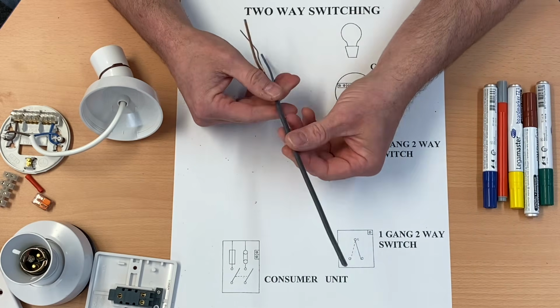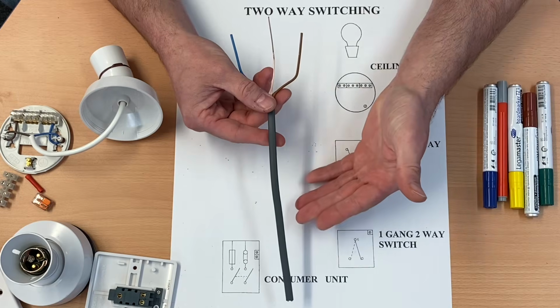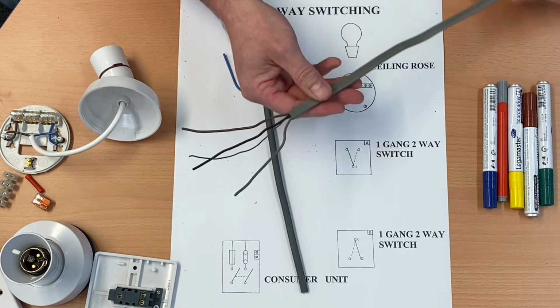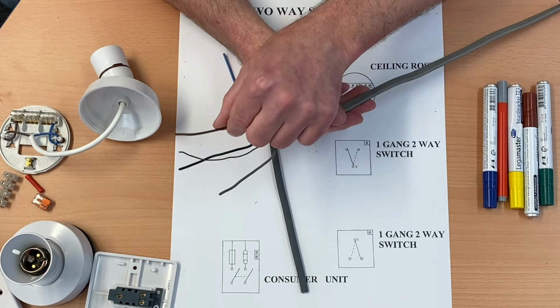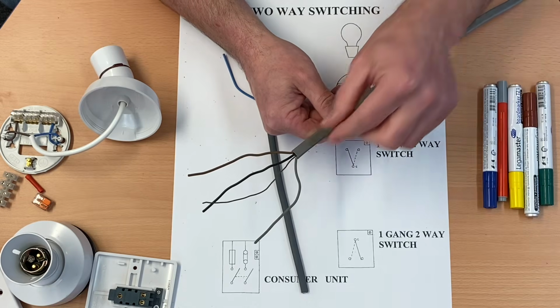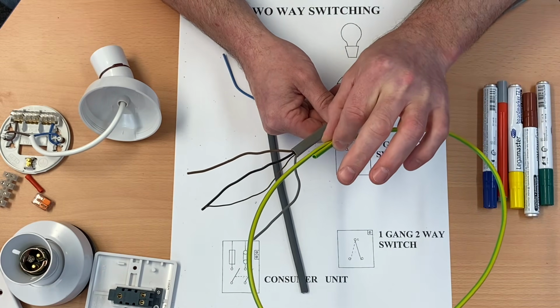Remember, we're chucking this cable away after each of our lighting circuits, so we might as well chuck away 1mm cable rather than 1.5. We're going to introduce a new cable as well, so we're going to have to use this cable here. This being a 3-core and CPC, so we've got brown, black, and grey, so we need those colours for our drawings as well, and a bare conductor again, which will be identified as our circuit protective conductor.